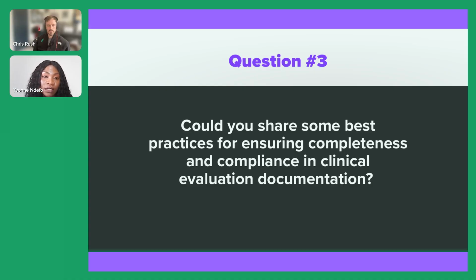Another piece of advice, which I touched on previously, is to familiarize yourself with the current guidance documents. As I said earlier, notified bodies still use guidance documents, and they will be using them to assess your submission. So you need to read the sections of the MDR relevant to clinical evaluation: MDR Annex 14, and MDR Annex 15 if you're performing a clinical investigation. If you're a legacy device manufacturer, you also want to familiarize yourself with MDCG 2020-6, especially Appendix 3, where it talks about what is sufficient clinical evidence and the whole hierarchy of sufficient clinical evidence. You want to familiarize yourself with all the guidance documents that are relevant, and you have to look at your device and see what's relevant and what clinical evaluation route you're choosing. So start early, and familiarize yourself with what's important.